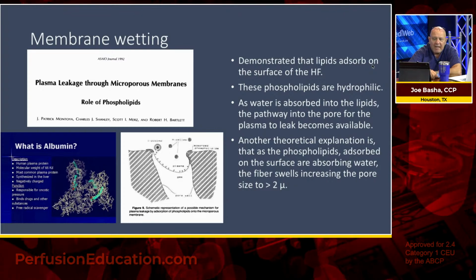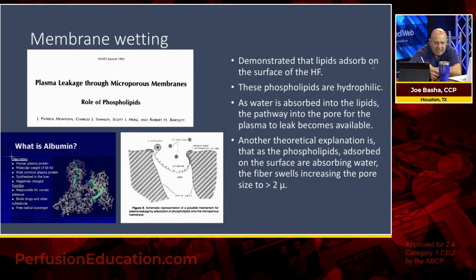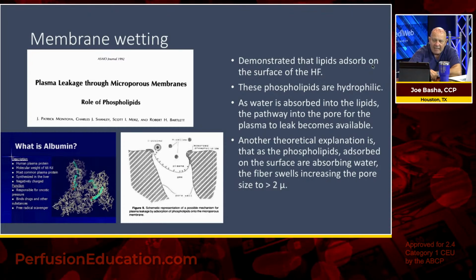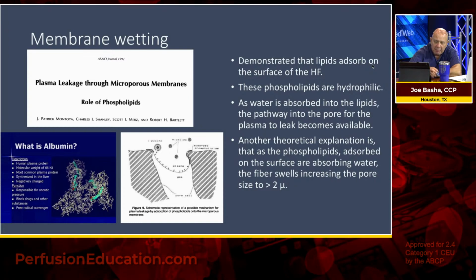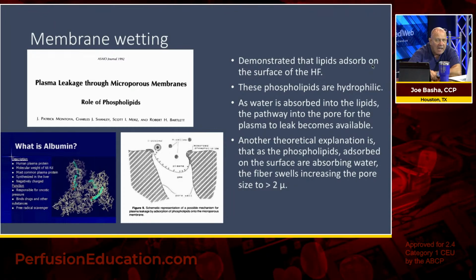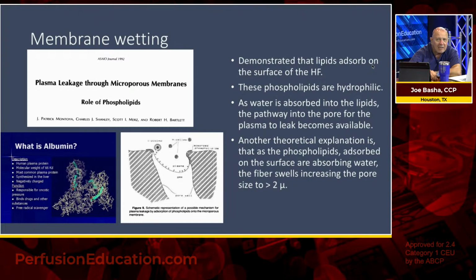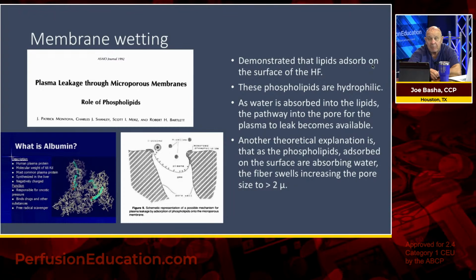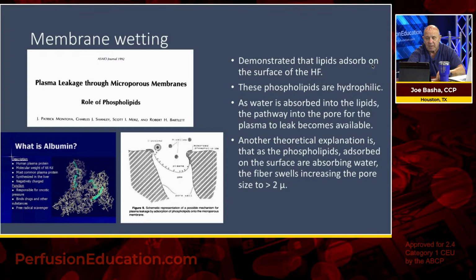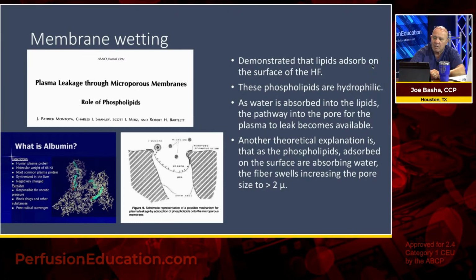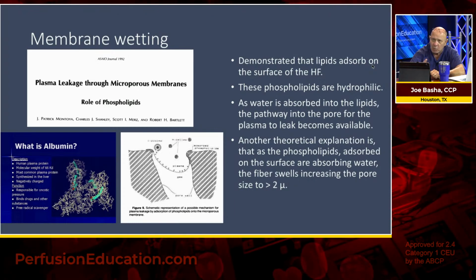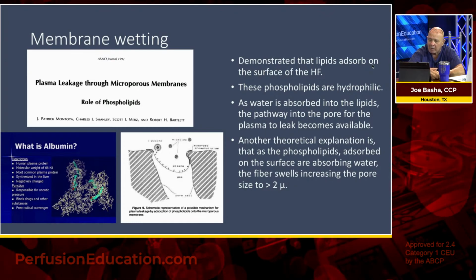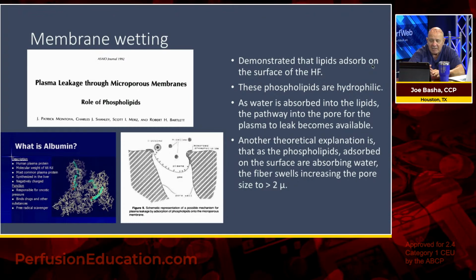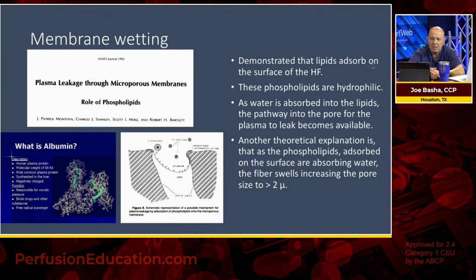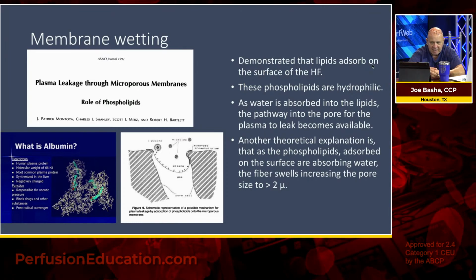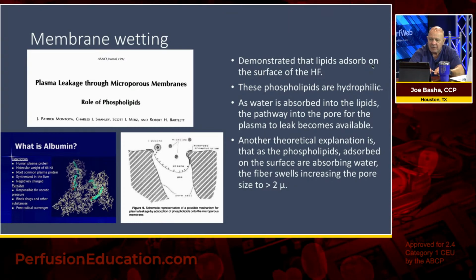So membrane wetting is a huge problem. Plasma leakage, whatever you want to call it, through microporous membranes. And the paper that was done in 1992, published in ASAIO by Montoya, describes in very nice detail why we were seeing plasma leakage or membrane wetting with long runs on polypropylene microporous hollow fibers. What he demonstrated was that lipids adsorb, not absorb, adsorb on the surface of the hollow fiber. These phospholipids are naturally hydrophilic. As water is absorbed into the lipids, it creates a pathway into the pore for plasma to leak.